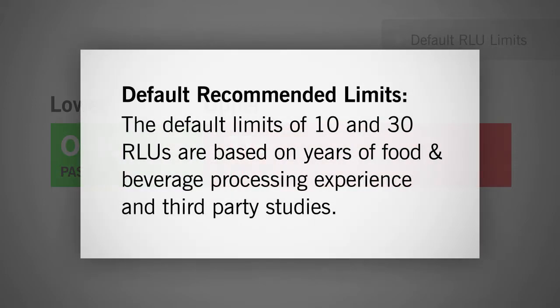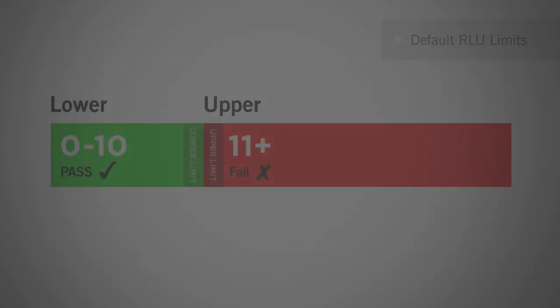The default limits of 10 and 30 RLUs are based on years of food and beverage processing experience and third-party studies. For more information, the ATP thresholds technical document is available at Hygiena.com. Download this document for your records or HACCP documentation.